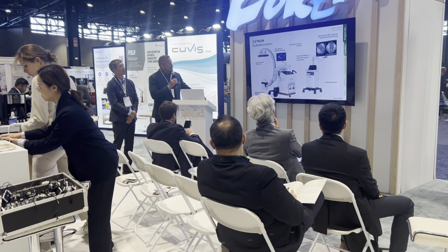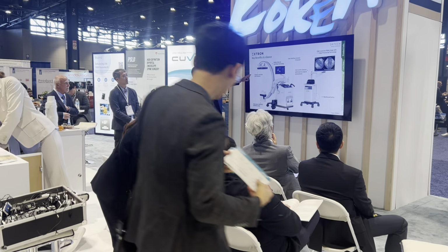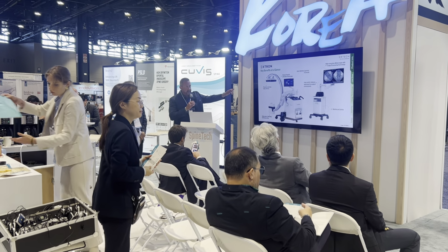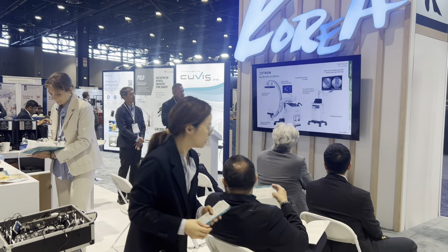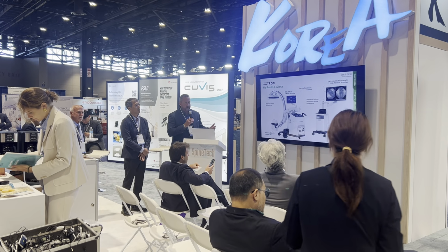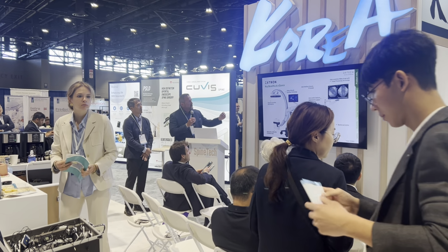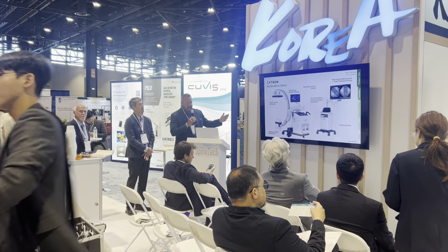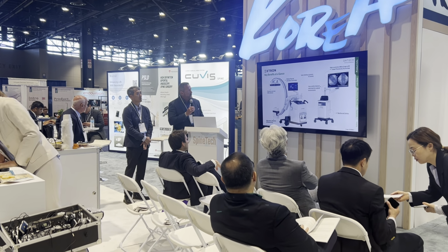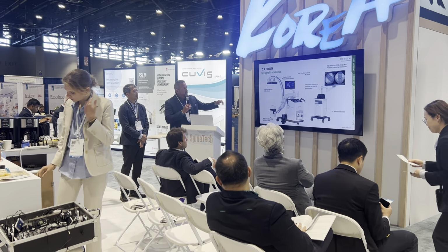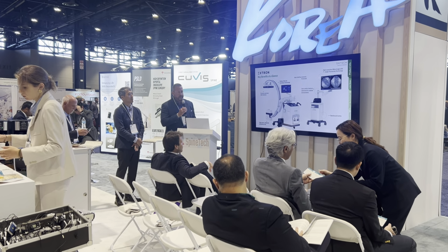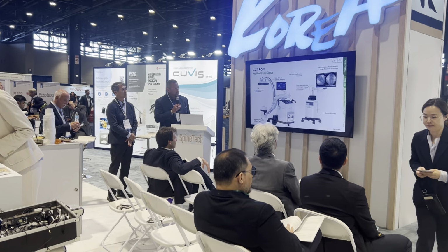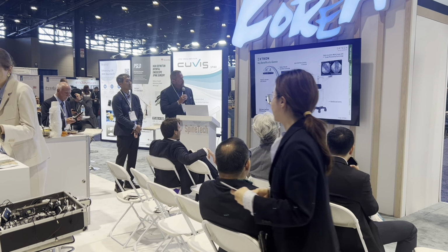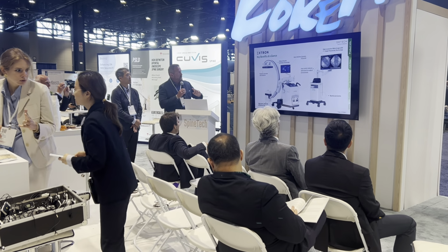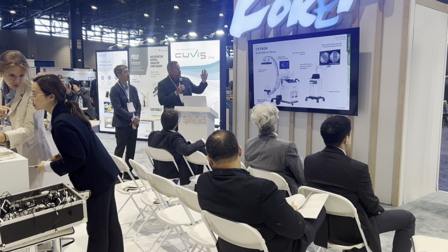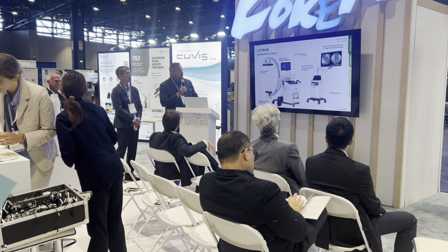So some of the things is they have the IGZO detector panel, which is developed by DRTECH, and they're the only C-arm company that developed their own flat panel detector. So that allows them to reduce radiation, improve image quality, and combine it with their C-arm. A lot of the other C-arm manufacturers buy the flat panel from somebody else and then integrate it with their C-arm. But because they manufactured it, they're able to really control it. Very low dose, very good image quality.